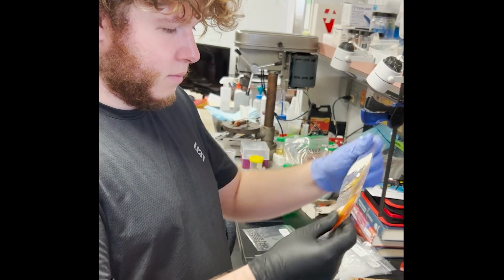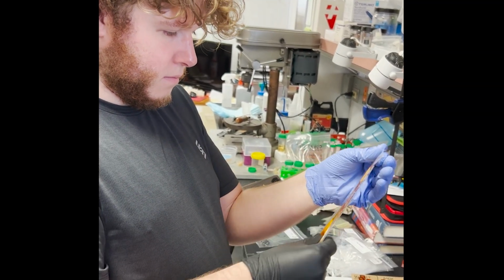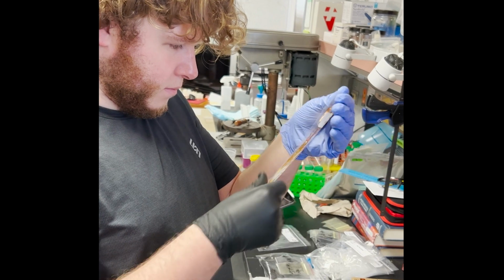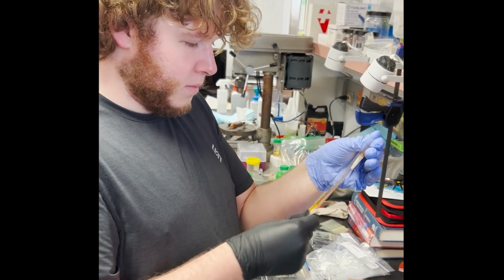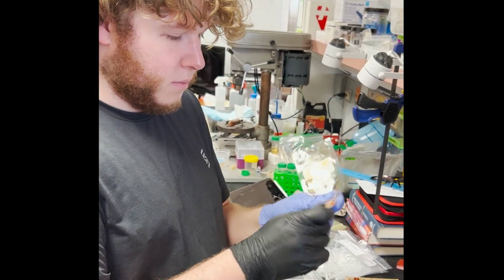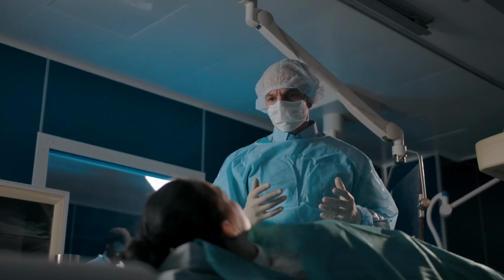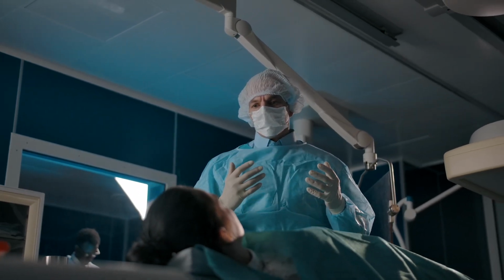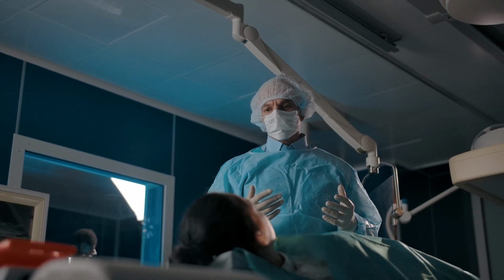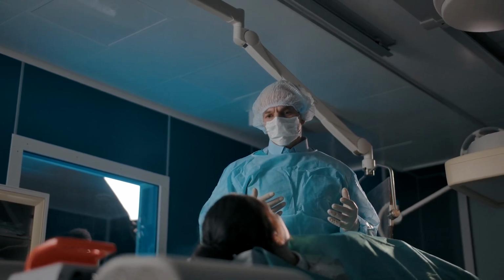Our safety procedures were met easily thanks to our selection of silicone-coated wires for proper electrical insulation, as well as the consideration we took in selecting the materials that satisfied the ISO 10993 biological evaluation of medical devices standard for cytotoxicity. Both safety procedures ensure that the patient is not being put in harm's way through the introduction of cytotoxic materials into their body, as well as protecting the surgical teams using the system from electrical hazards.